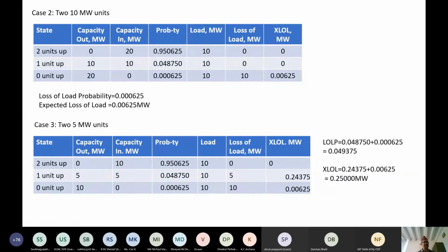Okay, this is the expected loss of load, and the expected loss of load is this much. Similarly, this was the second case, where we have 100% reserve margin. You can see if we go for percentage reserve margin, peak load is 10 megawatt. We have two 10 megawatt units, so percentage reserve margin is 100%.